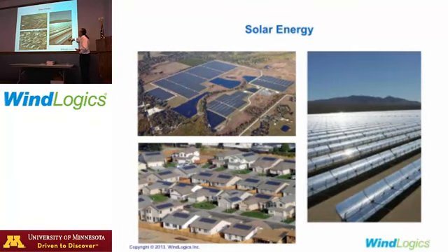This is a solar trough project out in the desert southwest. These have been around since the 80s. Some new ones are being built. These basically focus the sun, in this case, on a glass tube filled with a special oil. You create this superheated oil, which you use to create steam, run it through a steam generator just like you would with a coal plant. So that's a concentrating solar thermal project. There are other types that heat up molten salt on a tower, where they reflect all the light up to a point and do it with molten salt, a similar thing.